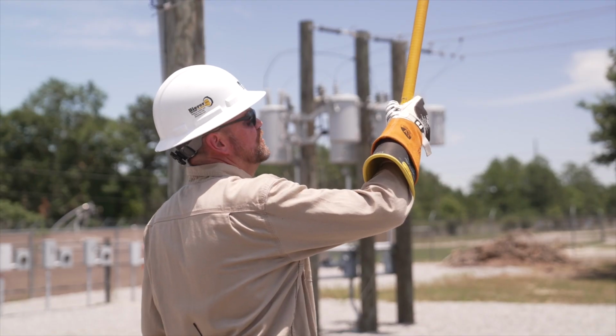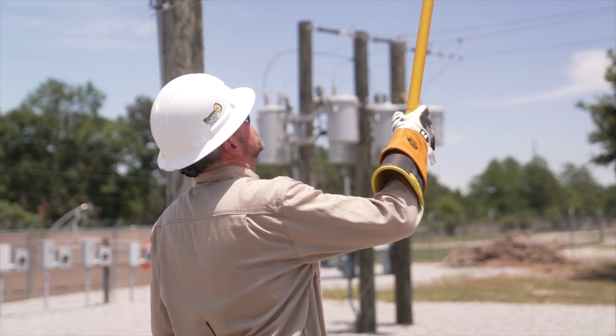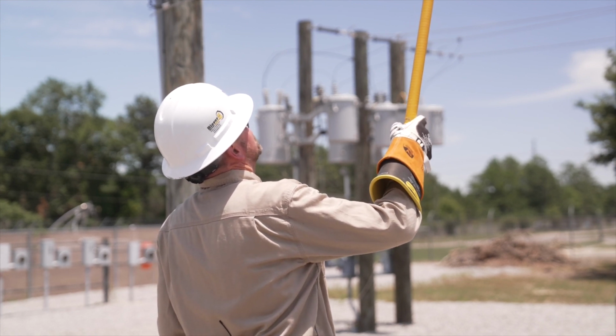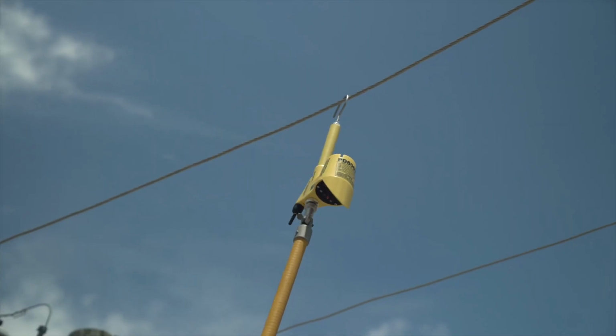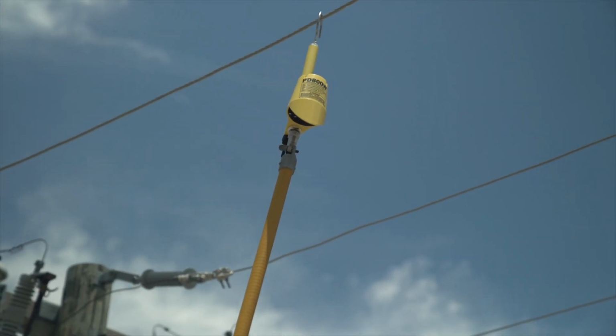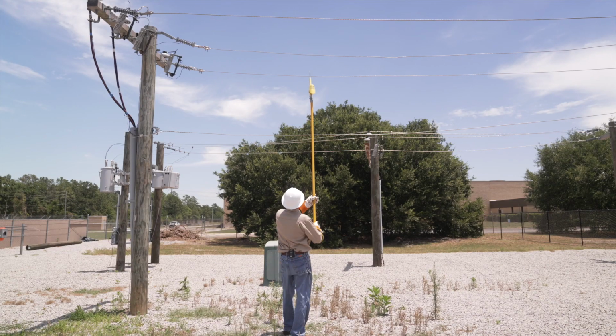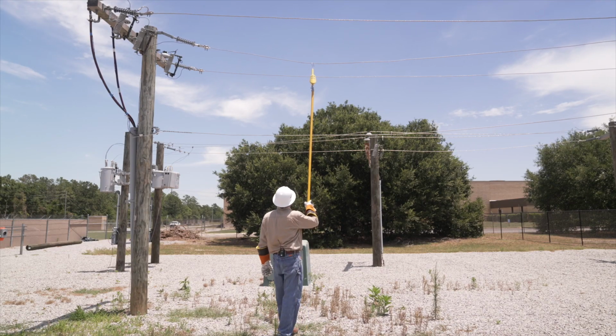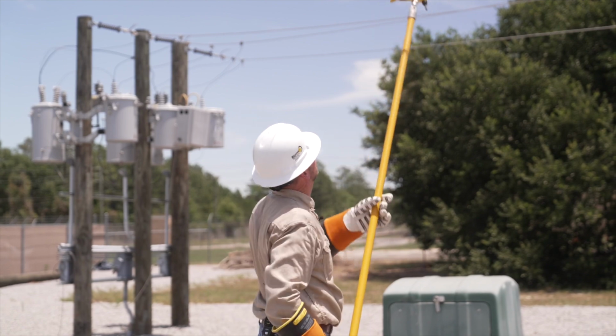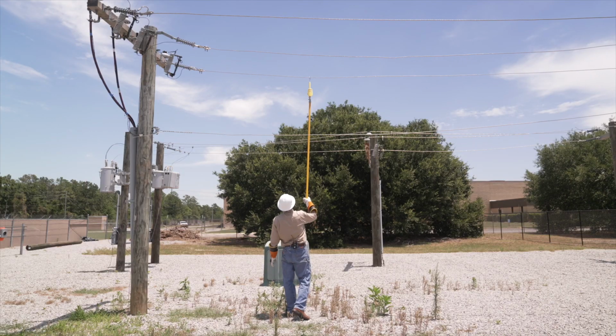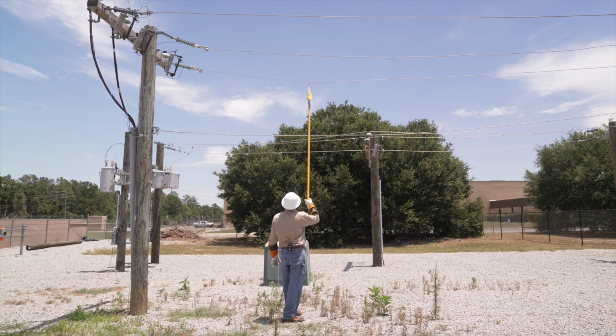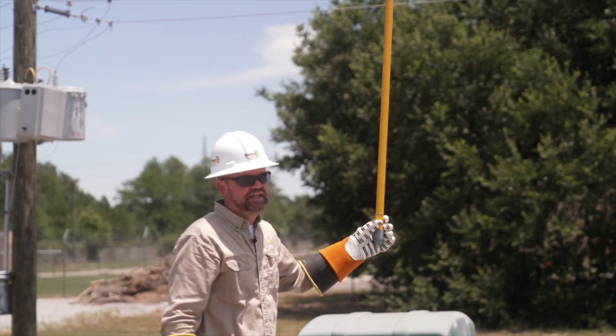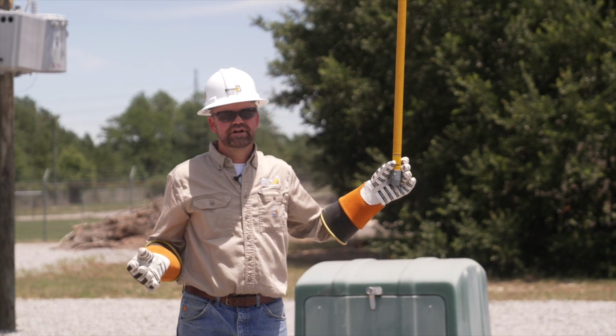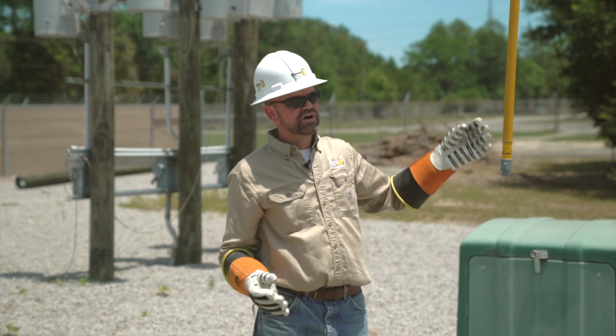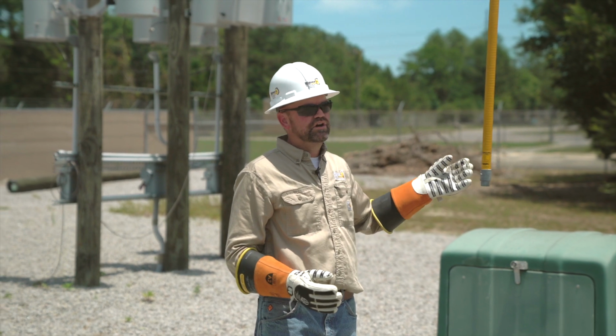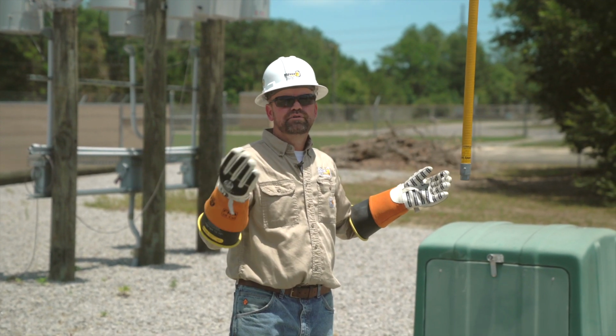So in fact, we did solve the problem. We fixed the problem. My phasing is good. My sequence is the same, it's good. In other words, my outside phase here is 240 degrees. My middle phase is my white light, my 0 degrees. And this outside phase is my blue light, my 120 degrees. So again, just like we did in our underground situation, we determine our sequence here. If we called this phase our field phase, we know our sequence is from road, middle, field.